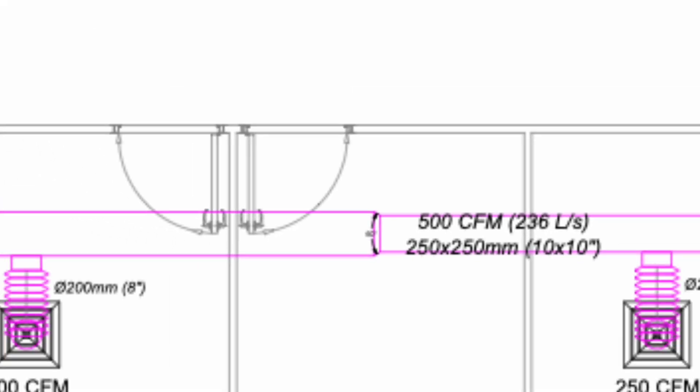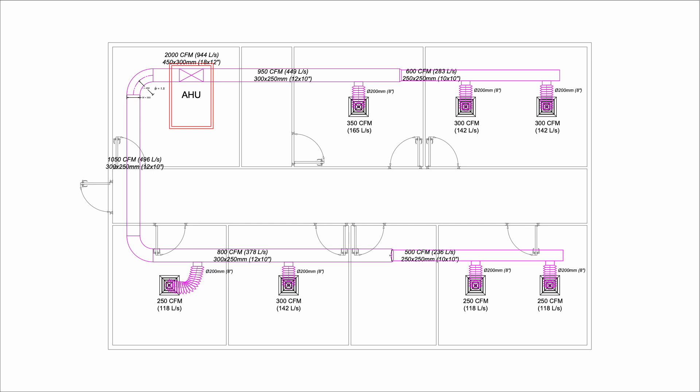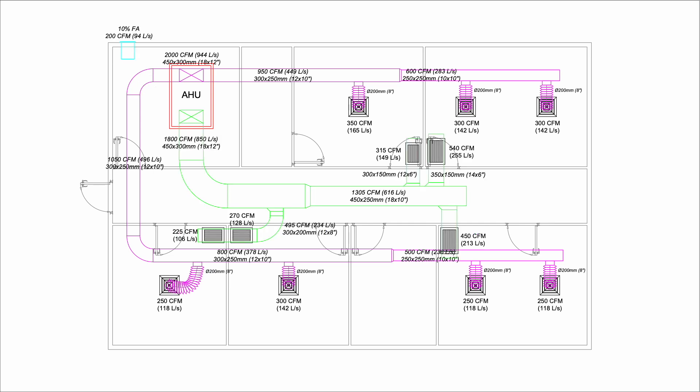Before we proceed to size the return duct, we want to consider bringing in some fresh air. Generally, the amount of fresh air is about 5 to 10% of the supply air. Here, I decided to bring in 10% fresh air which is 200 CFM. Therefore, the return air is 1800 CFM.